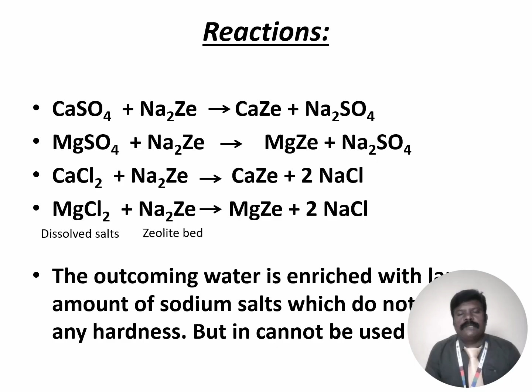What are the reactions taking place during this process? These are some dissolved minerals, which may be calcium sulfate, calcium chloride, magnesium sulfate, or magnesium chloride. Here is the synthetic zeolite, represented by Na2Ze, where the sodium ions are loosely held in the molecular structure so that they can easily exchange with calcium and magnesium ions. The sodium ions exchange only calcium and magnesium ions, not sodium ions, potassium ions, chloride, and sulfate ions. So the zeolite bed removes calcium and magnesium so that we get a water sample containing sodium sulfate and sodium chloride. This water sample is called soft water. The outgoing water is enriched with a lot of sodium salt, which does not cause any hardness, but it cannot be used for boilers since it may produce caustic embrittlement.